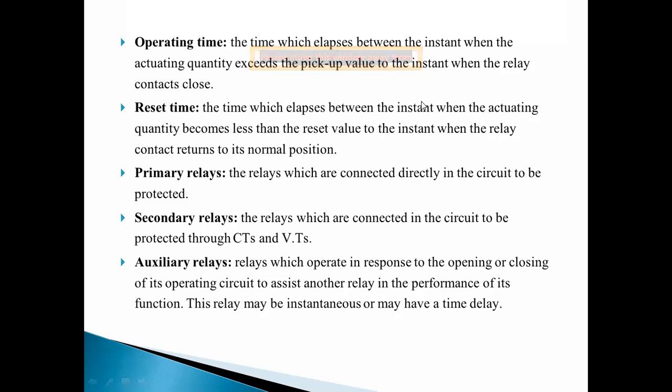Then what is pickup value? Value of actuating quantity. Then why is it called the pickup value? It is the border above which the relay operates. Yes, correct. It is the value at which your relay operates. That's why it is called the pickup value.